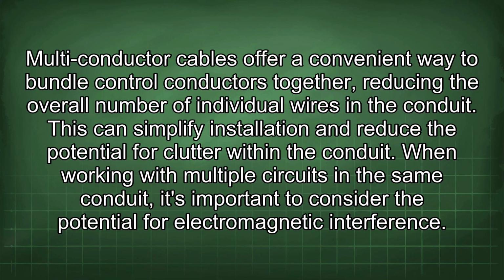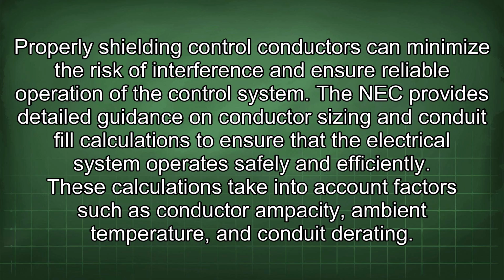When working with multiple circuits in the same conduit, it's important to consider the potential for electromagnetic interference. Properly shielding control conductors can minimize the risk of interference and ensure reliable operation of the control system. The NEC provides detailed guidance on conductor sizing and conduit fill calculations to ensure that the electrical system operates safely and efficiently. These calculations take into account factors such as conductor ampacity, ambient temperature, and conduit derating.